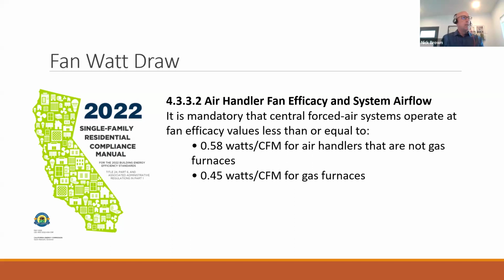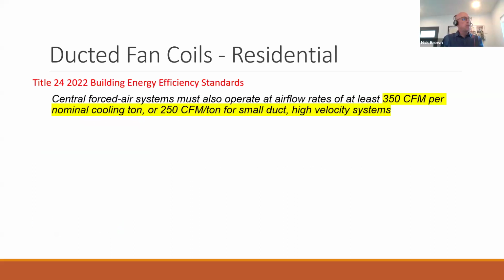That's great. Fan watt draw is another Title 24 required test. Your air handler fan is going to be measured, and the watts per CFM are regulated to 0.58 watts per CFM for a heat pump, 0.45, an even slightly harder target, for a gas furnace air handler. So if you have all kinds of duct leakage, you can have a hard time meeting this standard. The other one that Bobby alluded to before is the 350 CFM per ton requirement that we also have to test to with a HERS rater in California. That's another goal you're going to have a hard time meeting with leaky ducts.